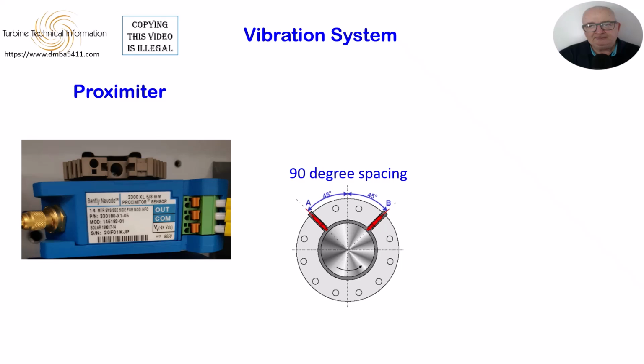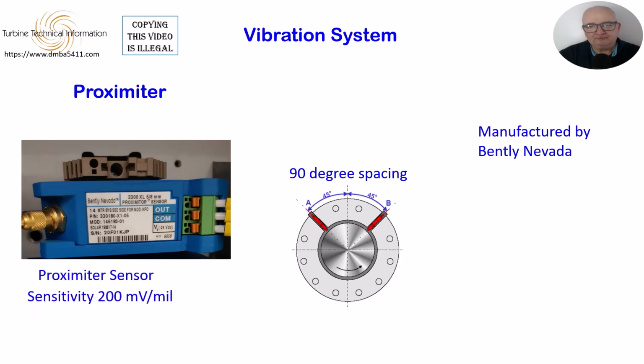Proximeters are made by Bently Nevada, and consist of an 8mm probe, an extension cable, and a proximeter. The proximeter sensor is seen in the photo. The proximeter produces a high-frequency signal that is sent to the probe via the extension cable. The magnetic flux produced at the tip of the probe creates eddy currents in the shaft, which then interact with the flux of the probe.